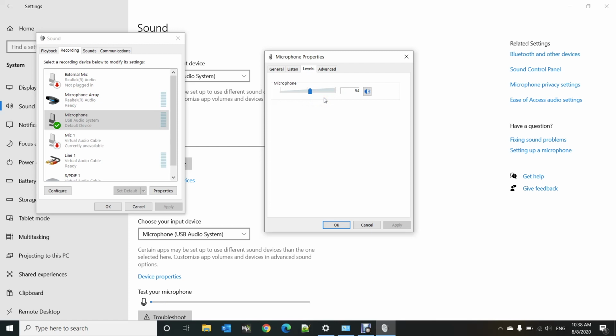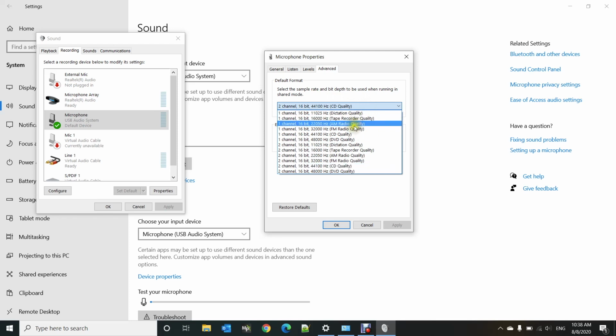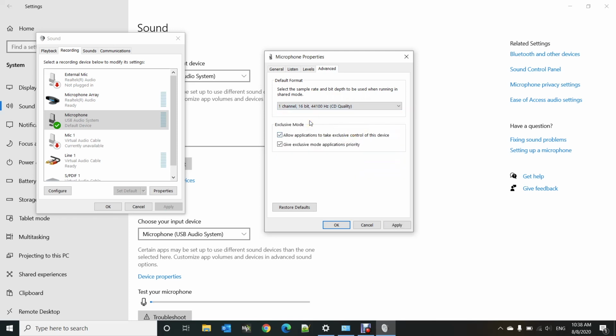So once that is set, click on Advanced, and you need to set the channels that you're actually going to be recording. Now, this is actually very important. Generally, when you open this for the first time, you may see this set as a one-channel system. Now, if you were to set it as one channel, the Impulse won't work correctly. In other words, you'll see a vibration signal on channel one, but you won't see the pulse signal for channel two. And I get a lot of questions from people out in the community about that.